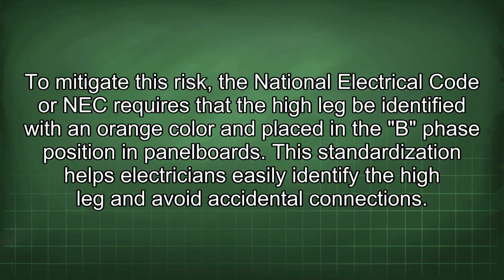To mitigate this risk, the National Electrical Code, or NEC, requires that the high leg be identified with an orange color and placed in the B phase position in panel boards. This standardization helps electricians easily identify the high leg and avoid accidental connections.